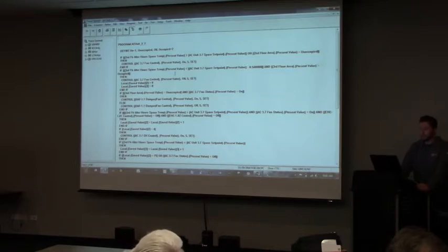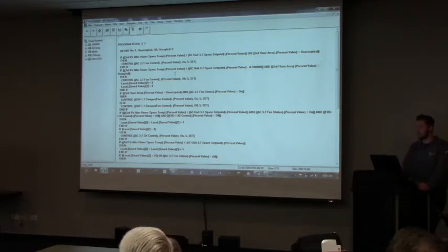So that's that. And this one's pretty simple actually. 3rd floor after hours space temperature present value: so just looking at whether the actual space temperature is greater than the actual space temperature set point, or 3rd floor area present value is unoccupied, then control 3.7 fan control on. So that's essentially how you read it. It's really not too bad.